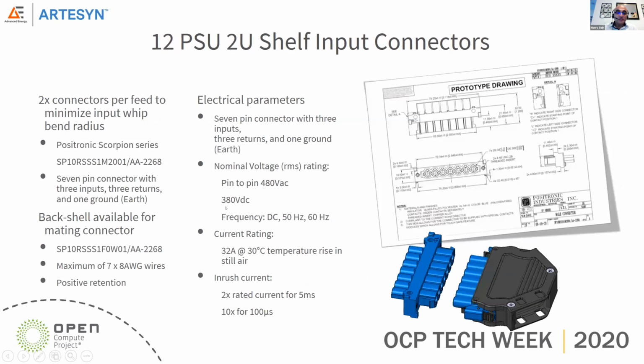Thank you, Ming. Moving on, to highlight the shelf input connectors: we can use either 2 input connectors, which are the Scorpion type positronic connector, or 1 connector. The advantage of using 2 connectors is that the big challenge, as we heard during the day, is the bending radius because of the large currents. That's a very challenging aspect. This design takes that stress out, and the bending radius for the AC input whip can be minimized. That's a great advantage of the shelf approach.